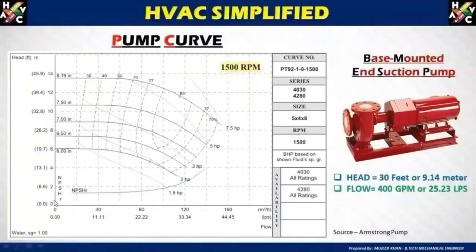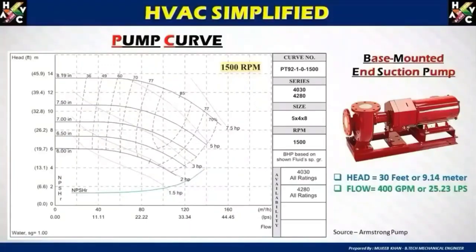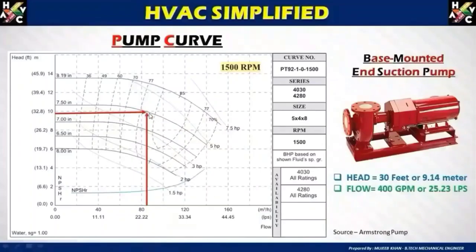On the x-axis there is GPM flow and on the y-axis there is the head in feet. The lines on the curve indicate the impeller size, the horsepower, and dotted lines for motor efficiency. Pump curve graphs are provided by all manufacturers depending on their sizes and capacities. For this Armstrong pump example, you plot a line from the x-axis at 25.23 liters per second and from the y-axis at 30 feet — the intersection point of these two lines is known as the operating point of the pump.